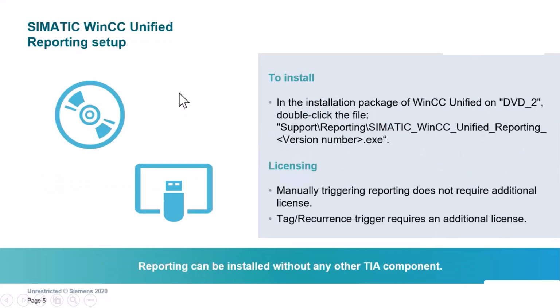Reporting is a core function of Unified, and its licensing is included with WinCC Unified Comfort Engineering. So to get this feature into place, visit DVD 2 of the installation disk for the TIA Portal version that is relevant to your panel's engineered runtime. Once the installation is complete, you will have components and tools for TIA Portal and a folder area where the Excel add-in will exist. This reporting installation can occur without any other TIA component installed.